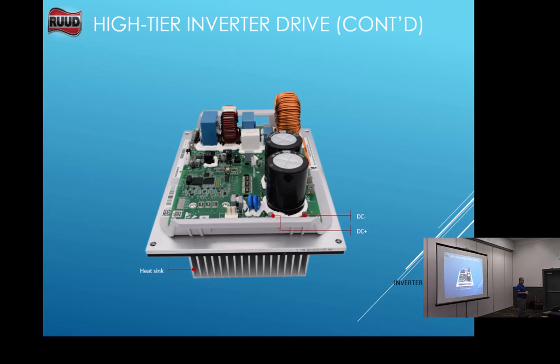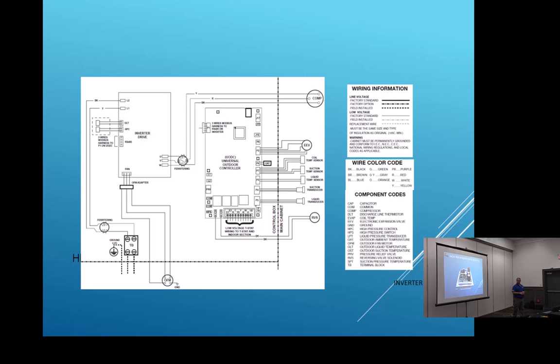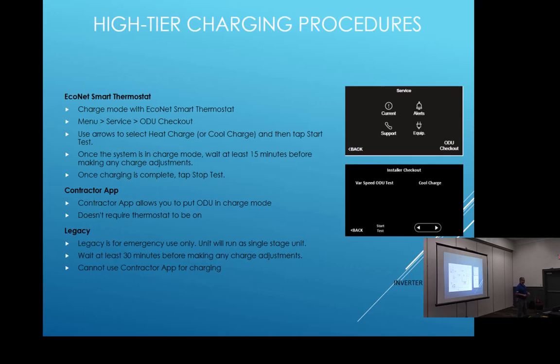The only difference in the high tier is the reversing valve. Wiring all is the same. Pressure switches and everything are all the same spots. The only difference is if it's a heat pump, you have a reversing valve hooked up. If you don't, straight cool, you don't have one. The high tier charging procedures, we have to have it in charge mode. So the high tier, we're going to have it in charge mode.